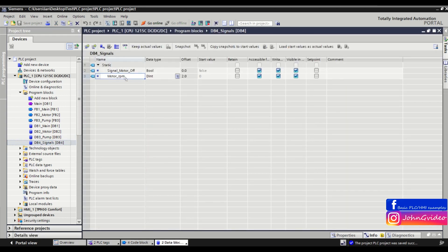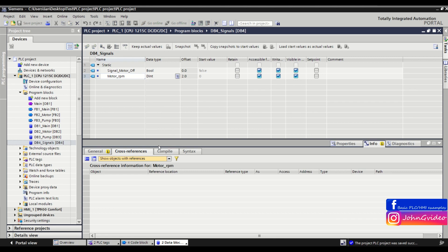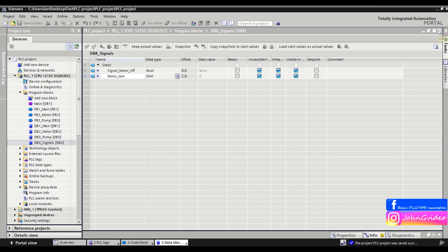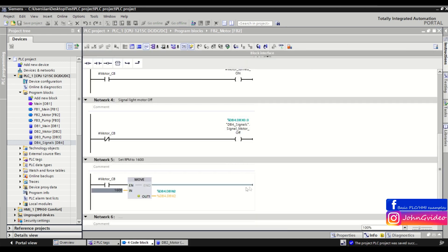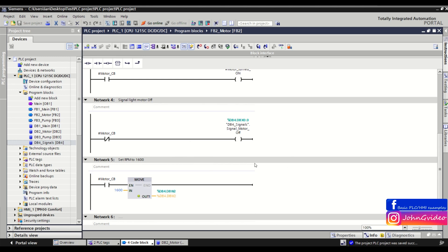To find where you use the motor rpm tag, you click on it, click on cross references, and you don't see any references to this variable. This is why it's better to always use normal symbolic access to variables. As you can see, there are no cross references.